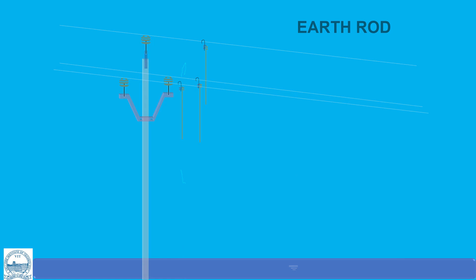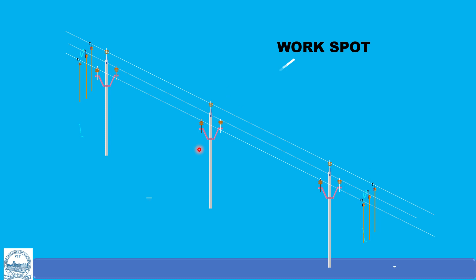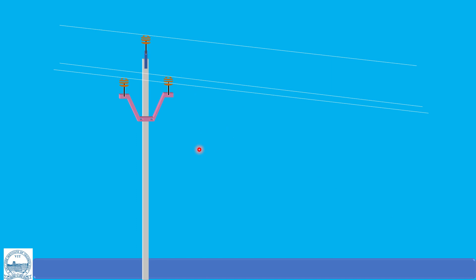So here you can see how the poles are mounted, and how the earthing rods are provided, mounted on the conductors. And here this shows in the work spot how the worker is protected. The grounding is provided on either side, that is on the incoming side and the outgoing side of the pole. We are connecting the grounding rods short circuited, so that whatever the direction of the power flow, it is completely bypassed here. If there is any leakage charge in this section, it is discharged here, and if there is any leakage charge in this section, that is discharged at this particular point, so that the person can work confidently without being subjected to electric shock.